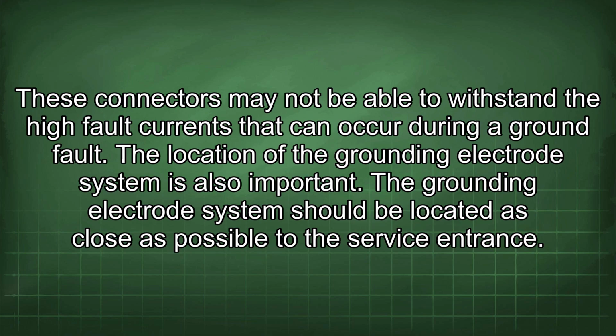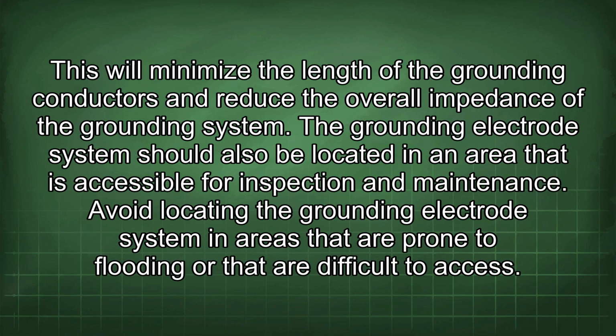The location of the grounding electrode system is also important. The grounding electrode system should be located as close as possible to the service entrance. This will minimize the length of the grounding conductors and reduce the overall impedance of the grounding system. The grounding electrode system should also be located in an area that is accessible for inspection and maintenance. Avoid locating the grounding electrode system in areas that are prone to flooding or that are difficult to access.